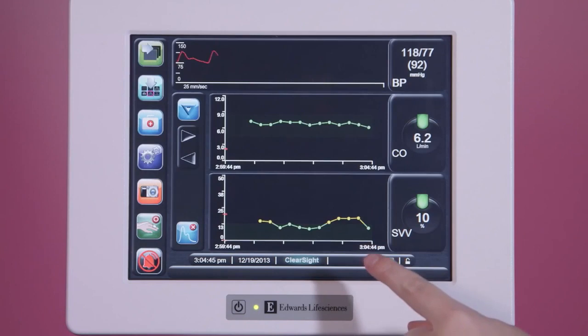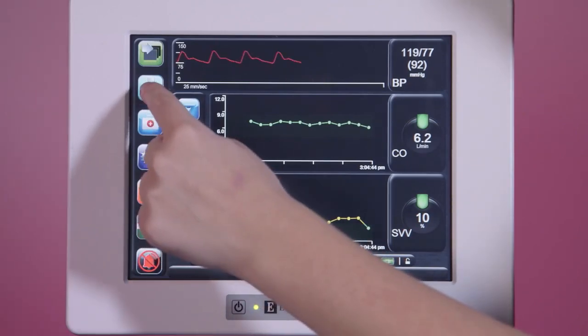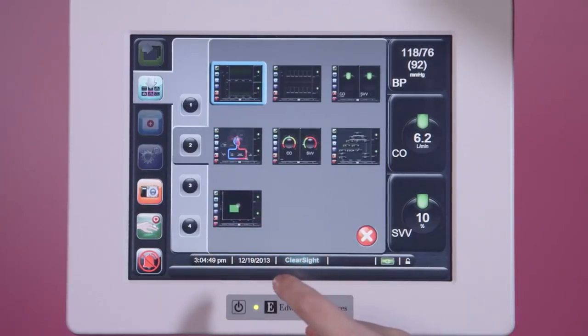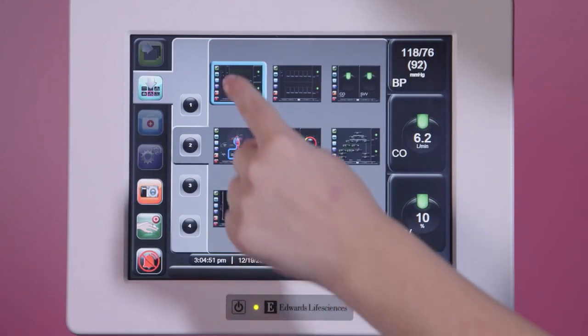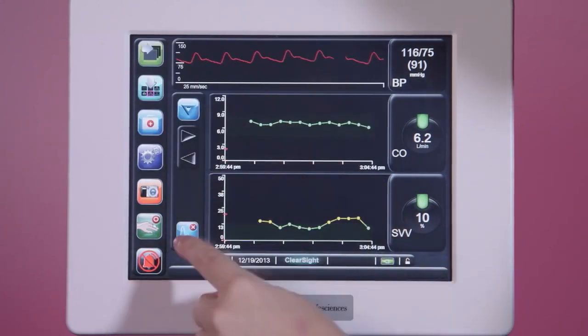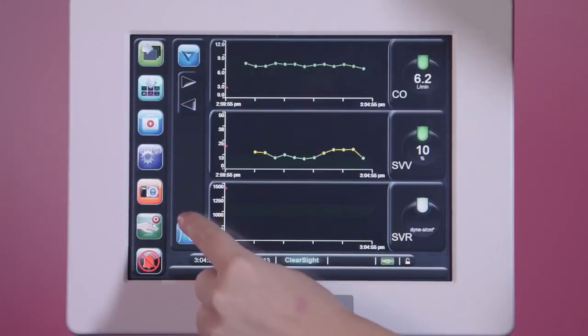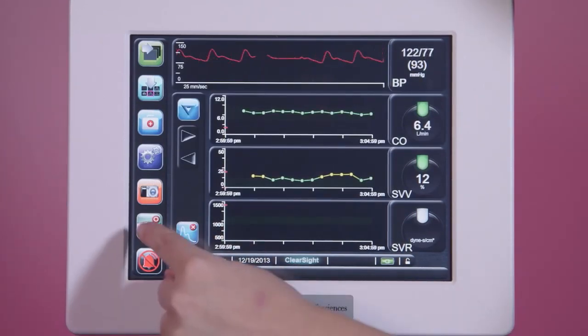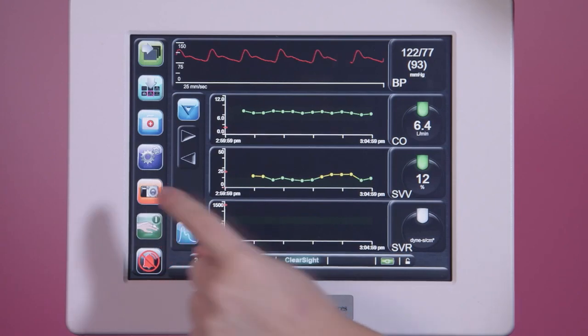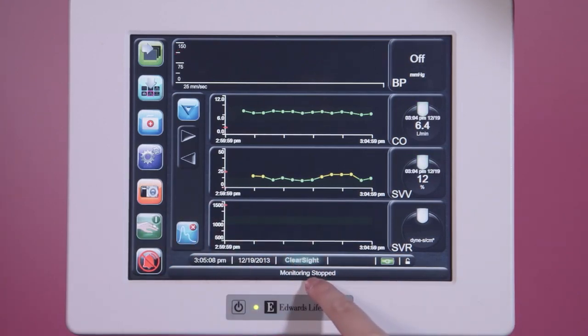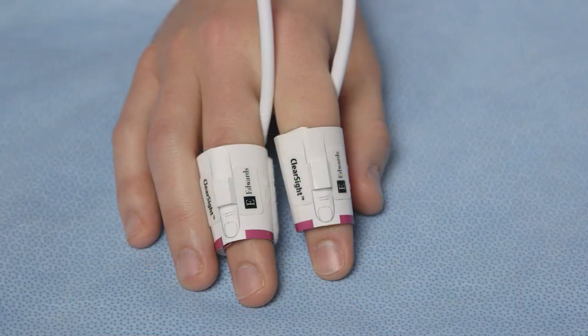You can now tap the screen selection icon on the navigation bar and select the trend screen. Tap the arterial waveform icon to display or remove the arterial waveform from the trend screen. When finished monitoring, tap the pump unit Start-Stop icon to stop the monitoring. The monitor will display Monitoring Stopped. Be sure to stop monitoring before removing the cuff. If removed while monitoring, damage to the cuff may occur.